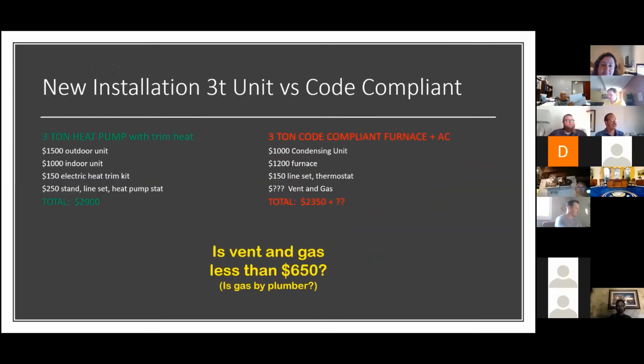Now, new installation versus code compliant. We looked at this pricing before, $2,900 versus $2,350. But we may have a little bit more electrical work on this side, maybe, but the vent and gas could easily be well above $650. Now, something to keep an eye on, if the plumber's doing the gas, you've got to make sure you're talking to the construction manager and get this credit out of the plumber's pockets and into yours. If you're doing the plumbing, great, I don't care, however that works out best.